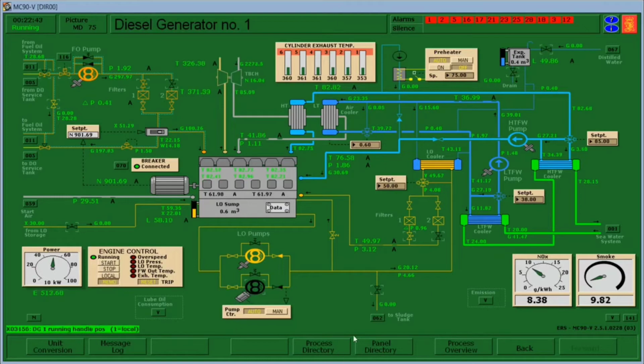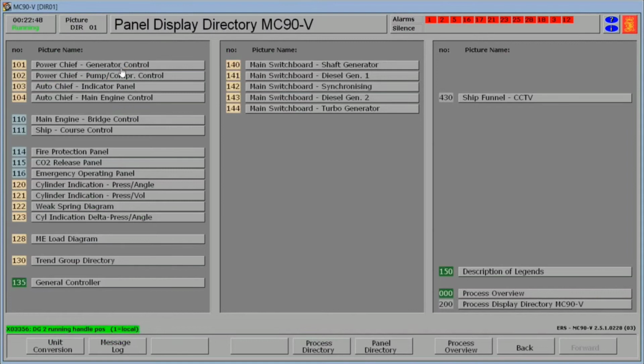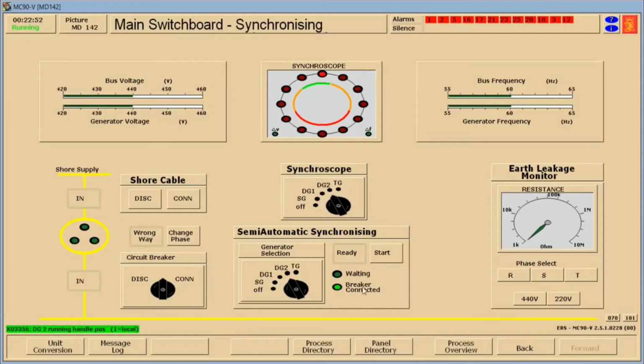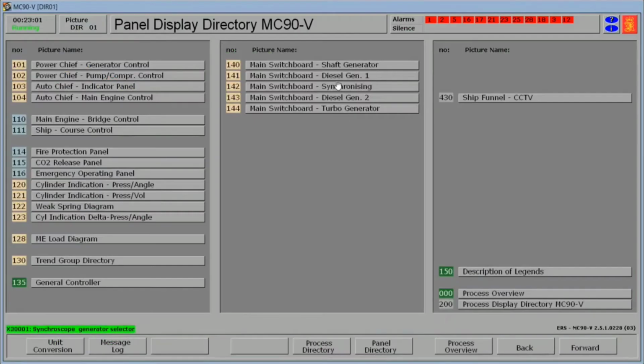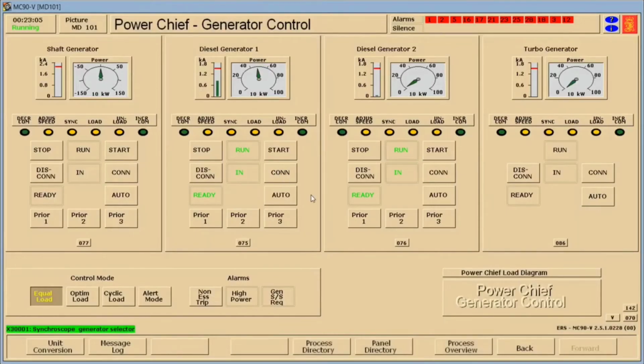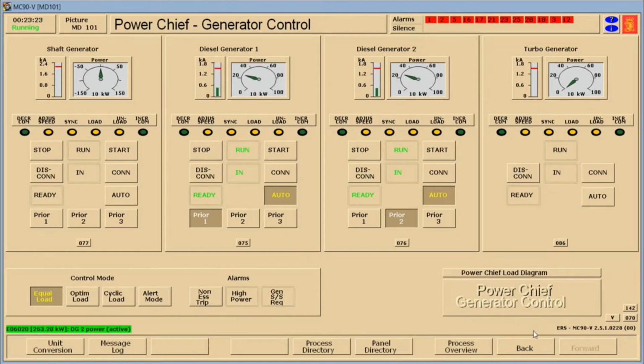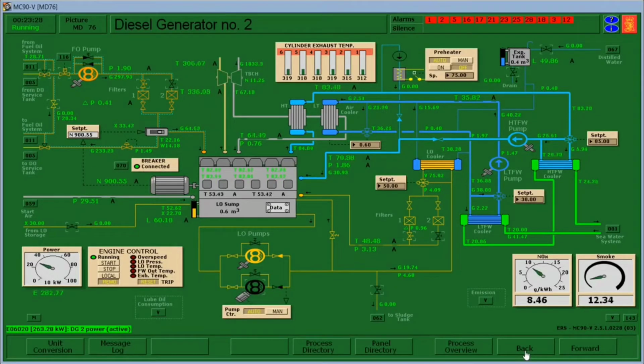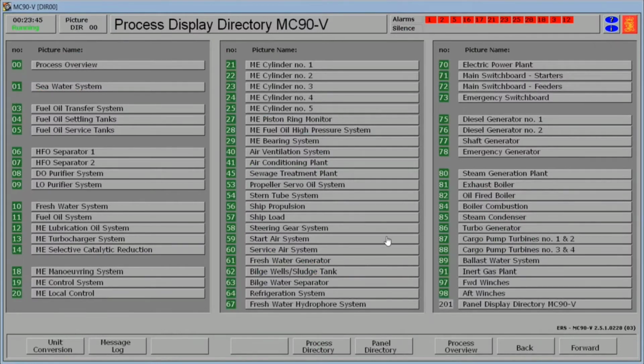So set the diesel generator number 1 to remote. Same for the diesel generator number 2. Proceed to switchboard, semi-automatic synchroscope off. Power Chief Generator Control set to auto, priority 1 and 2. Then they will share equal load. Notice that the powers of generator number 1 and 2 are the same. Okay, now the two generators are synchronized.